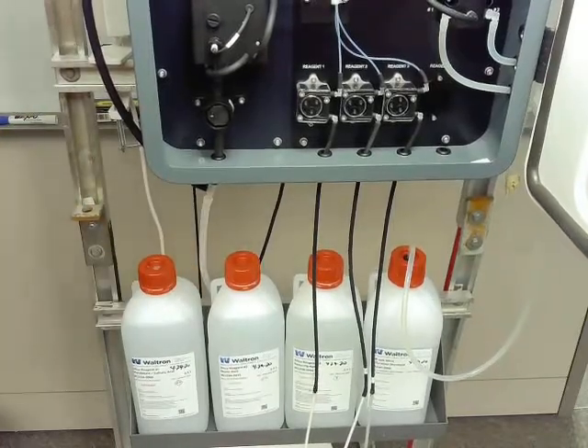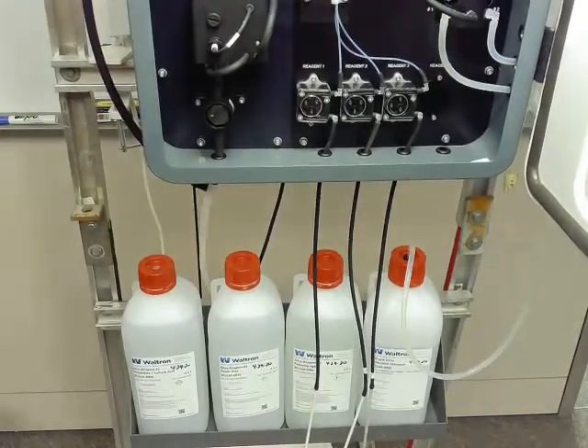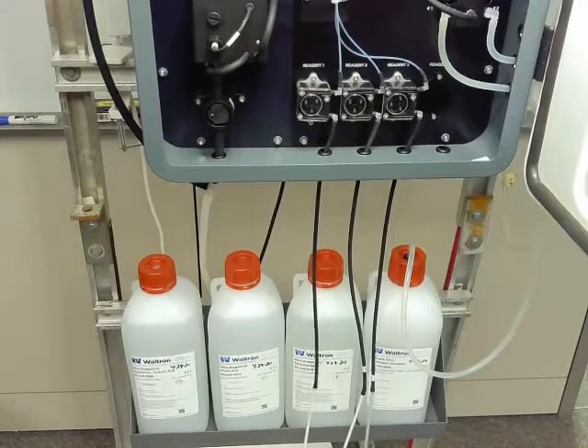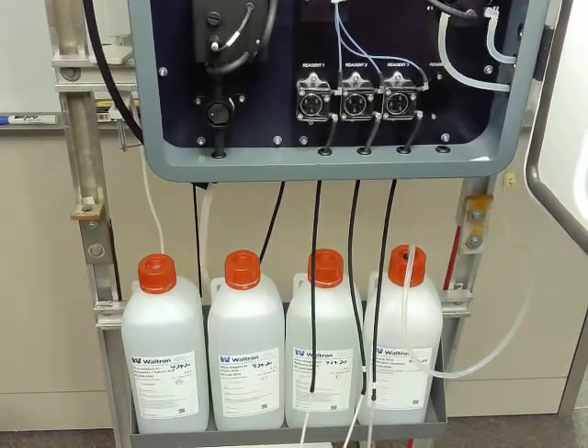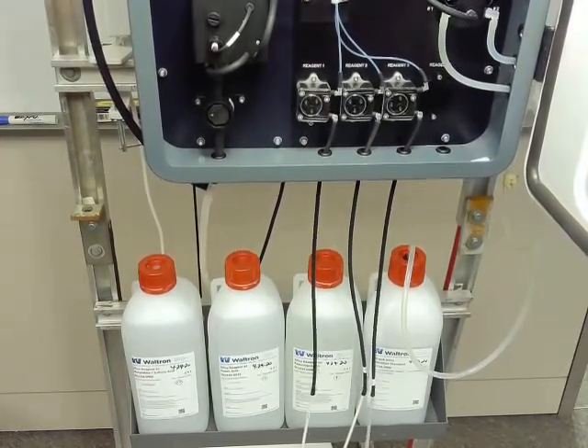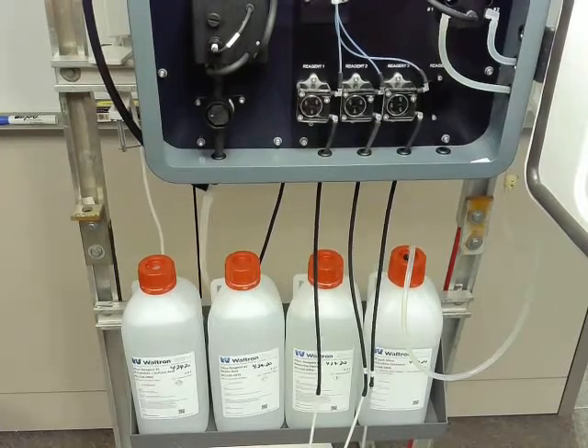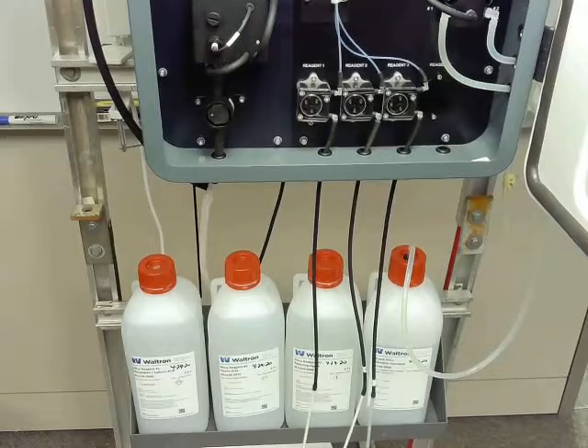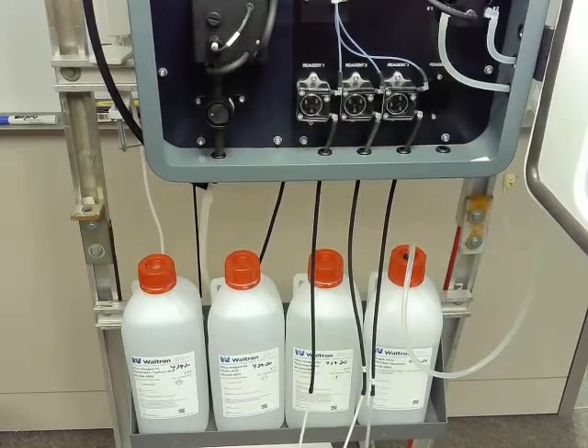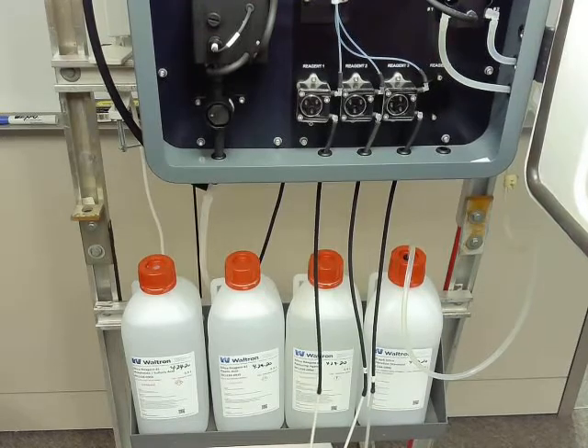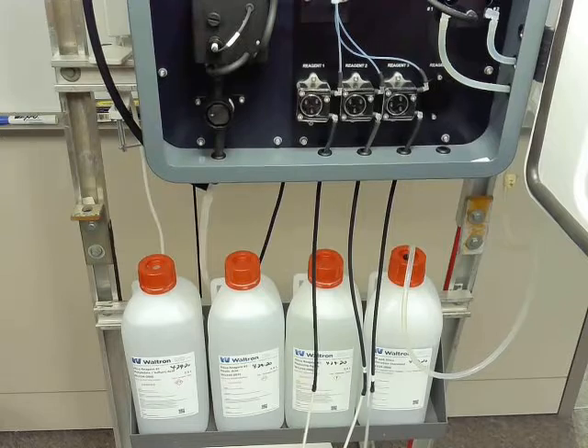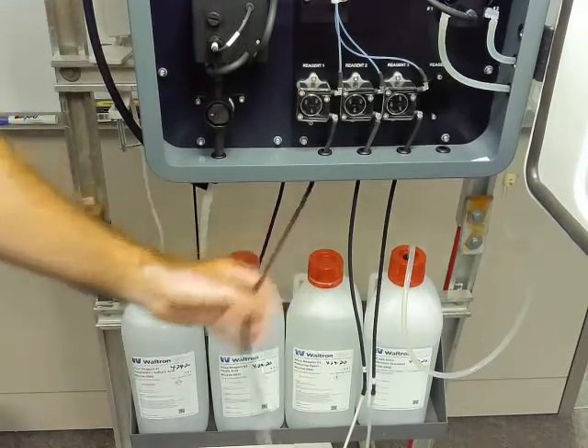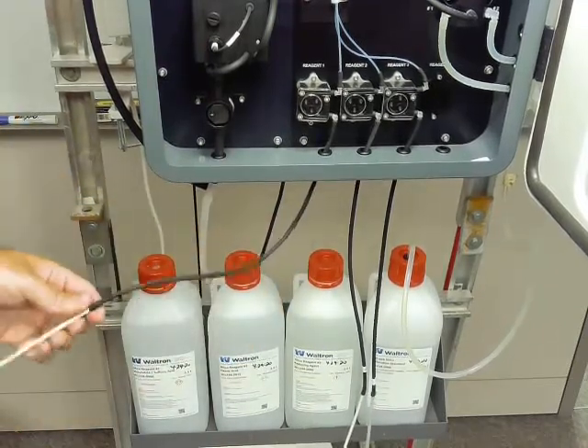So as far as installing the new bottle, your analyzer will alarm out at about 10%, and then at 4% it should kick into standby mode. It's always a good idea to discard everything that's left in the old bottle and open the new bottle up fresh. You don't want to risk contamination by dumping the last couple milliliters of whatever's in the old bottle into the new bottle. Just not worth that extra couple of readings you might get.